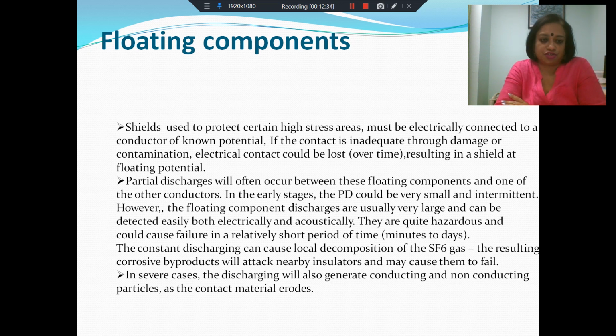If you have a metallic component at a floating potential, partial discharge can occur between this component and any neighboring conductors. In the early stages, the PD will be very small and it will come and go, so it may not be possible to detect it. But given a small amount of time, the floating component discharges become pretty large, and therefore they are comparatively easier to detect, either through electrical measurements or acoustic measurements. This is important because PD at floating components can be quite hazardous and very likely to cause very quick failure. Within a matter of minutes to days, it can cause failure.